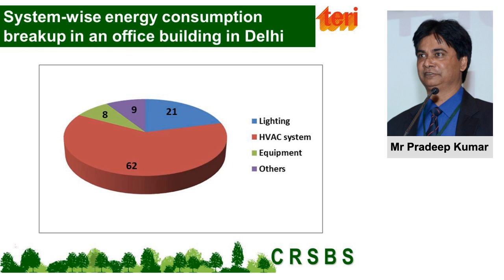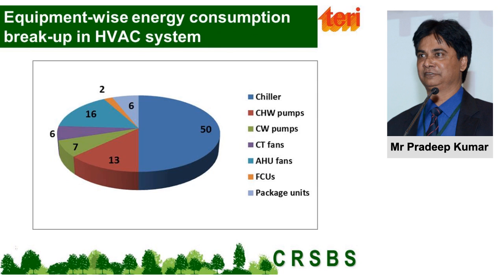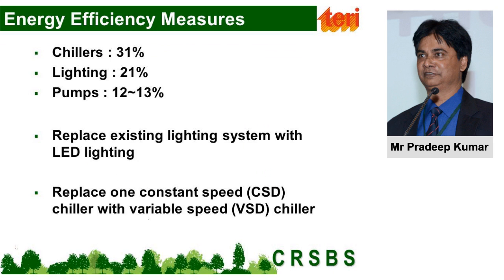Now, within the air conditioning system, almost 60% of the total energy consumption, the chiller, which is responsible for generating chilled water, which is used for extracting heat from the spaces or conditioning the spaces, consumes 50% of that. And pumps roughly 20% or so. So if you look at it, chillers consume 30% of the total energy, lighting 21%, and pumps somewhere around 12 to 13% of the total energy consumption. So that's why these are the three load centers or energy systems, always very important when we plan to improve the energy efficiency level or maturity level in buildings.